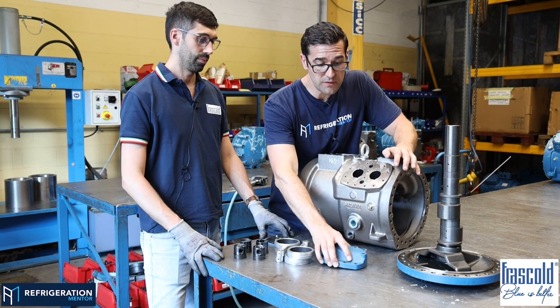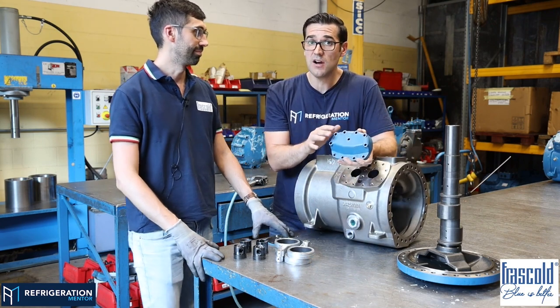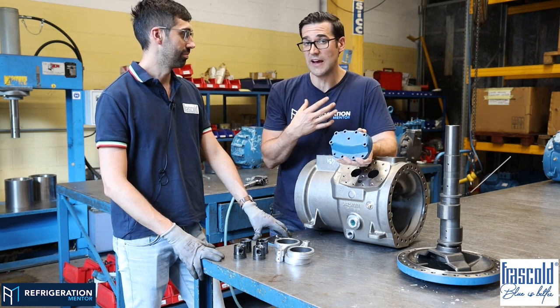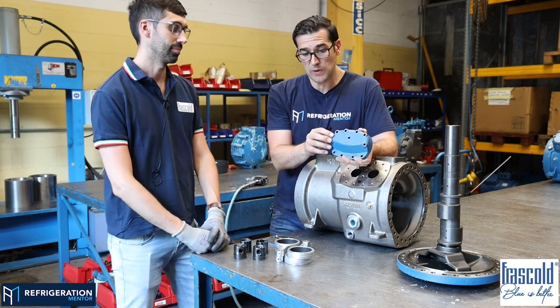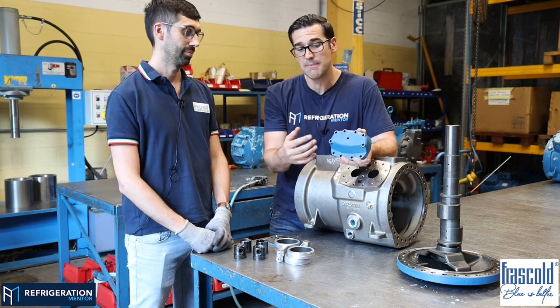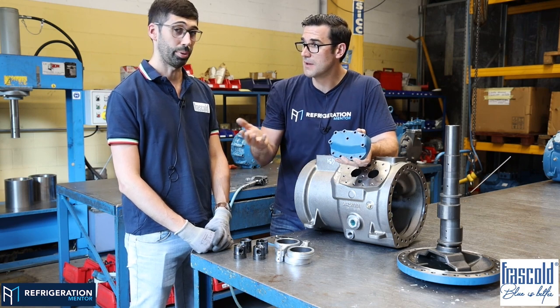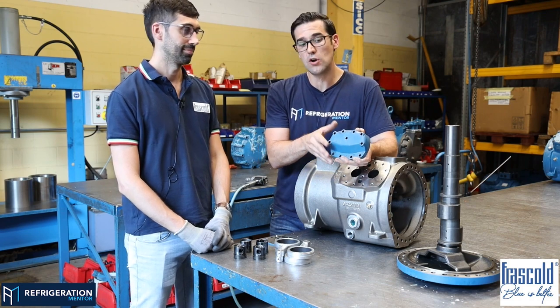So the other thing that we said is the torque value. 100% every time you need to go into the documentation, unless you remember. I don't remember the torque value, and you got to go in and match it up. So M8 bolts, like we talked about, is going to be different than M10. So I talk about inch pounds, and then you talk about Newton per meter. It doesn't matter what the units are. You want to make sure you torque them properly.